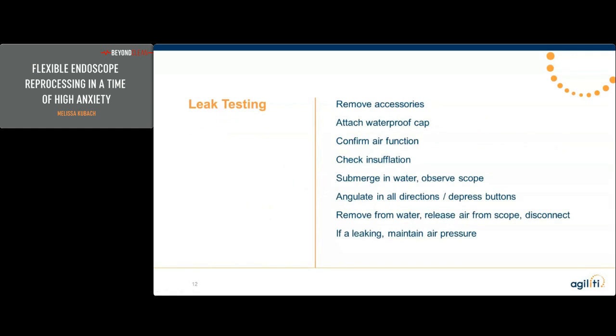Leak testing is the one thing everyone can do to help protect the patient and protect their equipment, not only from damage and repair costs but also downtime. Proper leak testing includes removing all accessories prior to the test, attaching the waterproof cap, confirming air function and that your leak tester is working, making sure the scope holds insufflation for safety before it goes into fluid, submerging it in water alone, observing the scope, angulating in all directions, depressing and manipulating the video buttons, removing it from the water, releasing the air, then disconnecting, and if it is leaking, maintaining air pressure through the entire cleaning process.